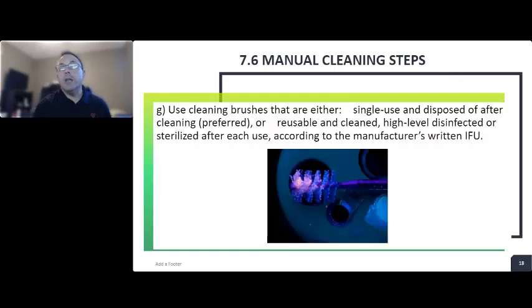So I travel the country, I go to lots of places, and people bring me in when they're having struggles with cleaning devices, and they say, hey, we're really struggling. I walk into a facility and I see all their brushes laid out. And I used to believe that in our industry, it was specifically stated that we should only use single-use brushes on flexible endoscopes. Well, the truth is that's not actually accurate. So use cleaning brushes that are either single-use and disposed of after cleaning, that's preferred, or reusable and cleaned, high-level disinfected or sterilized after each use according to the manufacturer's written IFUs.